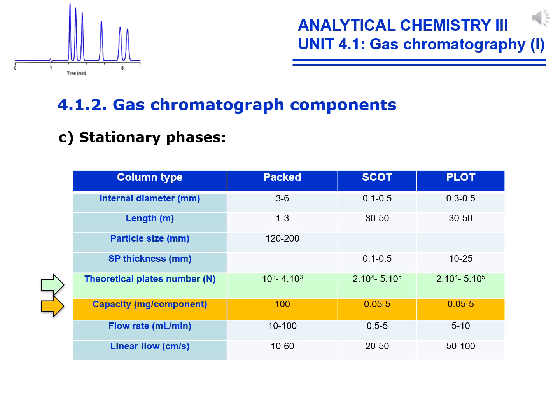The table on the slide summarizes the characteristics of packed columns versus capillary columns. The great use of capillary tubular columns is mainly due to their high efficiency, highlighted in green, 30,000 to 50,000 plates compared to 2,000 to 4,000 of a packed column. On the other hand, the high efficiency of this type of column allows good resolution to be achieved without resorting to highly selective stationary phases.